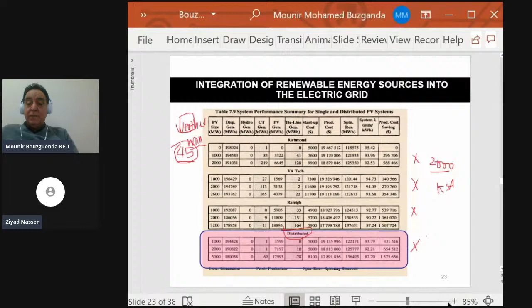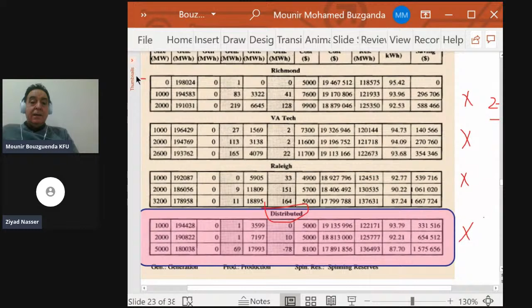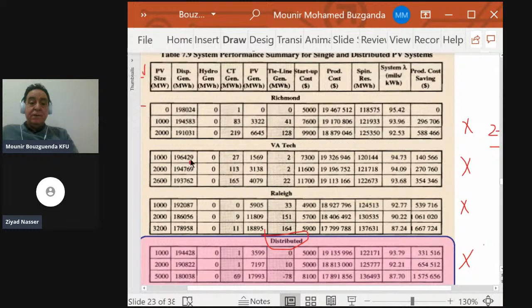So we can increase the system here. I'm looking at the maximum PV system accepted. I'm going to change the size of this. This is the PV size accepted, without any issue. I mean, that's what the system will accept. So if you have it in one place, in this case, for example, Richmond, the maximum level is 2,000 megawatt, 2,600 megawatt in VA Tech, and 3,200 in Raleigh. And for a distributed system, the maximum level is 5,000 megawatt. So you can see that having the solar PV system, or actually the entire system, distributed over 3, 4, 5 areas will improve the acceptance of the solar PV. It will increase the penetration level of the system.